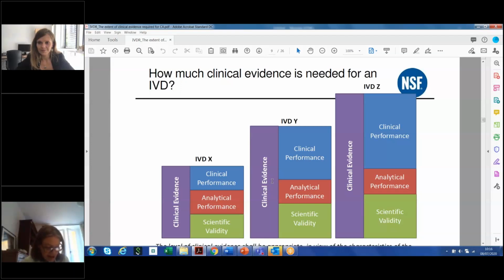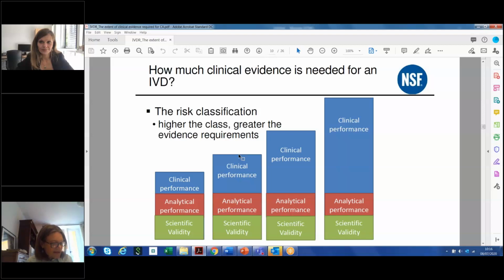There is a caveat to this in that we are informed in the regulation that if testing in an end-user setting is omitted, it should be justified that the internal conditions of use, for instance, your R&D laboratory, cover the normal conditions of use as described in your intended use statement and in Annex 1. So let's start looking at some aspects that impact on the amount of clinical evidence required. Remember, every IVD is unique based on its intended purpose and its manufacture, and all the following aspects that I'm about to discuss must be considered when judging how much evidence you will need.